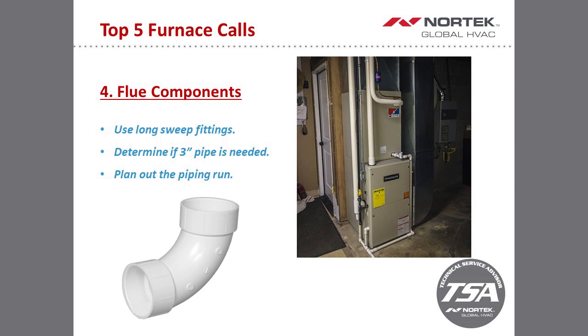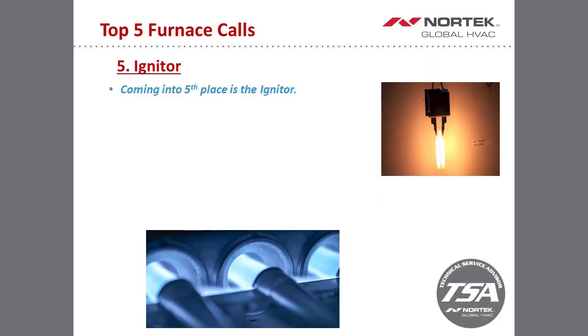So, sometimes that'll be different depending on the installation and what you're having to work with. Also, as a side note, you never want to transition to 3-inch on a horizontal run, because that won't allow the water and condensation to drain back into the drain system of the furnace, and you'll end up stacking water. So on that 2-inch to 3-inch fitting, just make sure that's on a vertical run and you'll be just fine. The next one that we'll talk about here is the igniter.